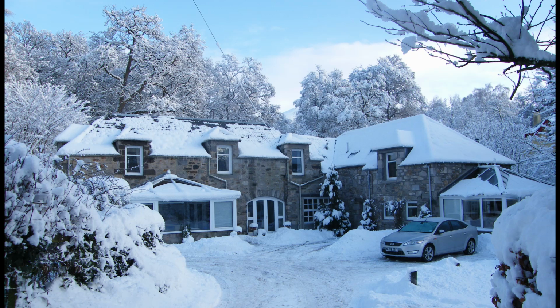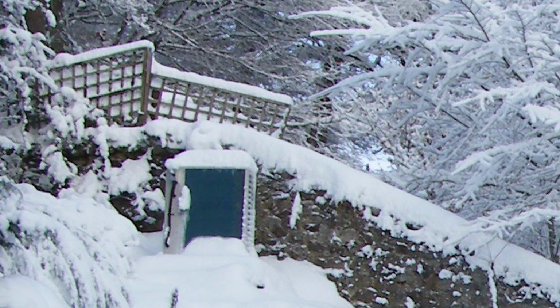The pictures I'm showing you here are of our heat pump, which we installed in 2009 in the Cairngorm National Park, which is one of the coldest parts of Britain. The air contains moisture, so when it's blown over the cold heat pump radiator, the water will frost up on the radiator. In order to keep the heat pump radiator clear of this frost, it has a defrost cycle which warms up the radiator and melts the frost. Defrost cycles are particularly important for the efficient performance of your heat pump.